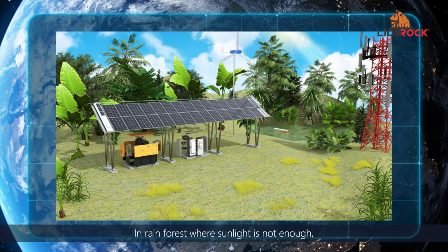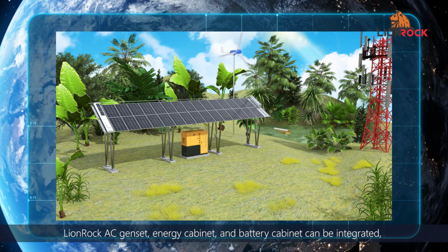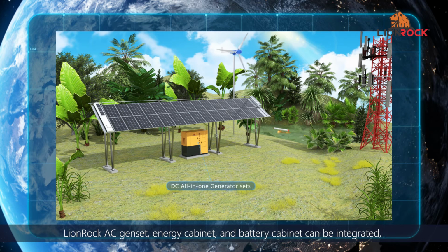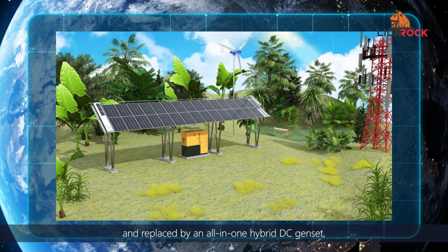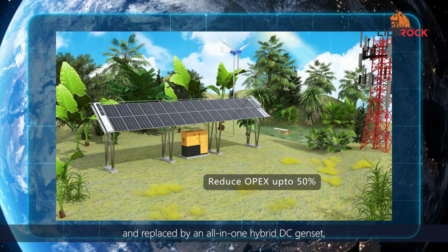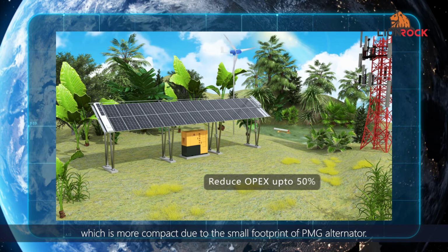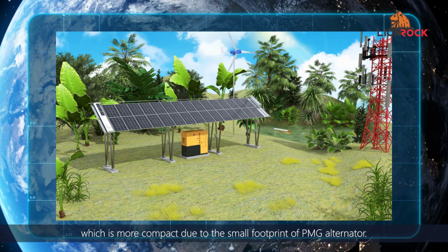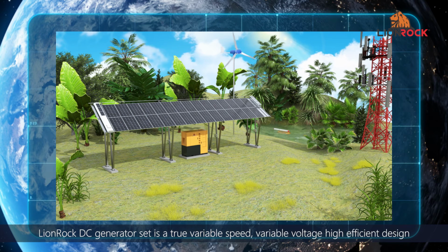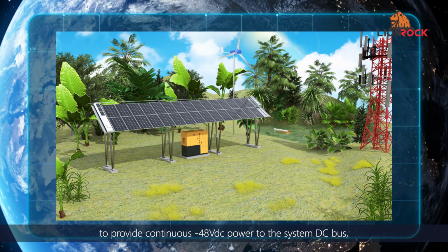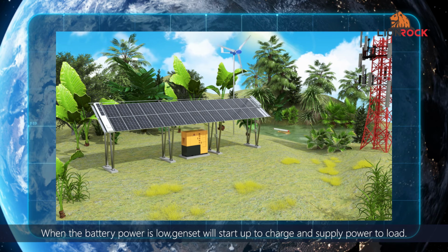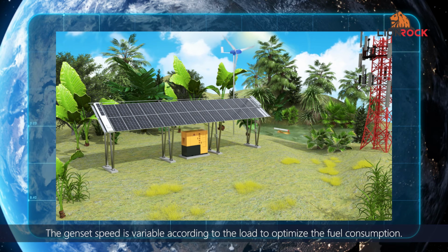In rainforest where sunlight is not enough, the LionRock AC Genset Energy Cabinet and Battery Cabinet can be integrated and replaced by an all-in-one hybrid DC genset, which is more compact due to the small footprint of the PMG alternator. The LionRock DC Generator Set is a true variable speed, variable voltage, high efficiency design to provide continuous minus 48 volt DC power to the system DC bus. When the battery power is low, the genset will start up to charge and supply power to the load. The genset speed is variable according to the load to optimize fuel consumption.